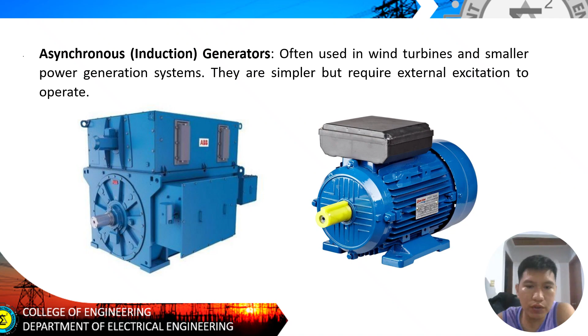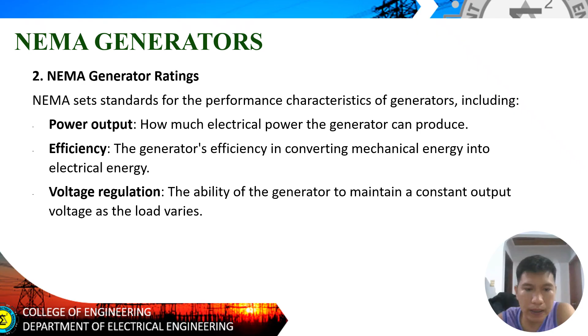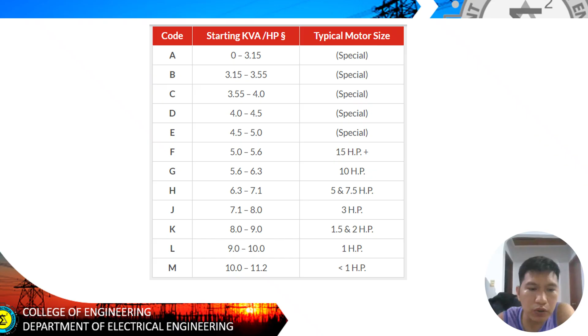NEMA generator ratings. NEMA sets standards for the performance characteristics of generators, including power output, efficiency, and voltage regulation. Meron tayong mga code. Generator codes A, B, C, D up to M. Yung rating kVA nila, and typical motor size: 15 HP plus, 10 HP plus, 5 and 7.5 HP, 3 HP, 1 HP, up to less than 1 horsepower. Typical motor size.